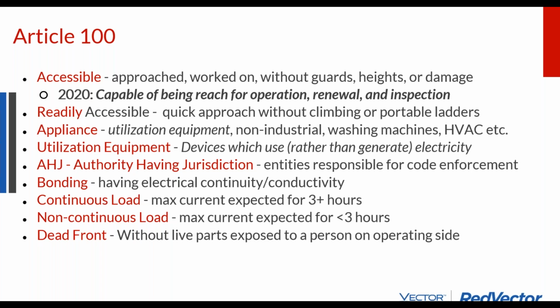The big thing here is the difference between accessible and readily accessible. The main thing is something that's readily accessible has to be approached without climbing or the use of a ladder, whereas accessible is something you can walk up to, but you might have to climb over something to get to. So you can have an accessible box in your attic, but a readily accessible item could not be in the attic. At any rate, this knife switch on the outside of the building needs to be readily accessible.